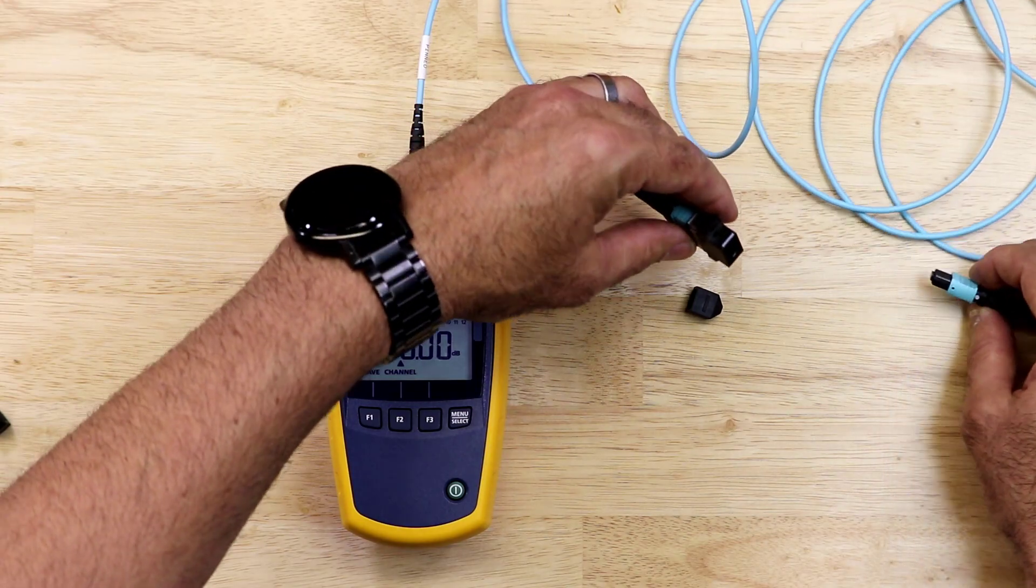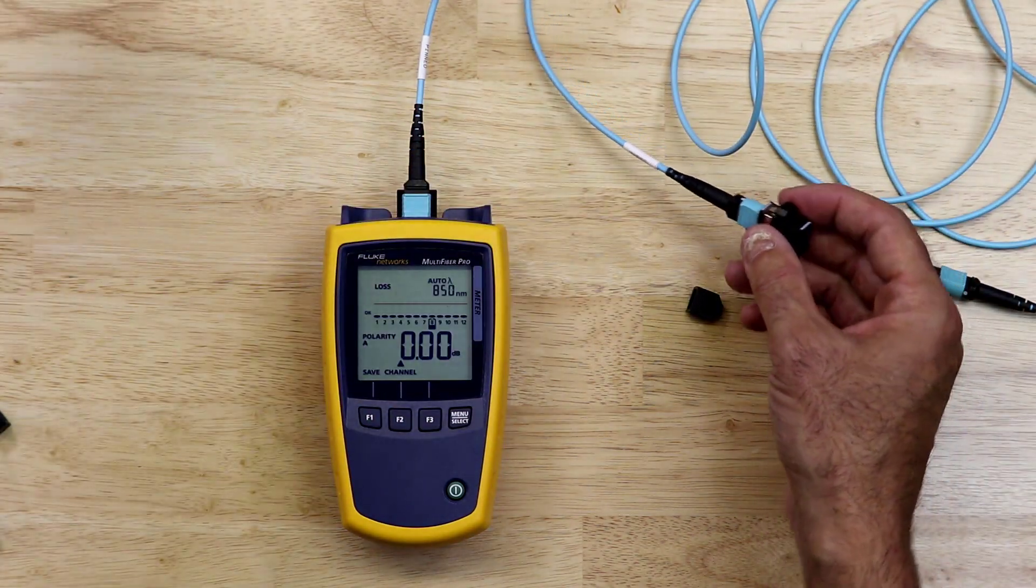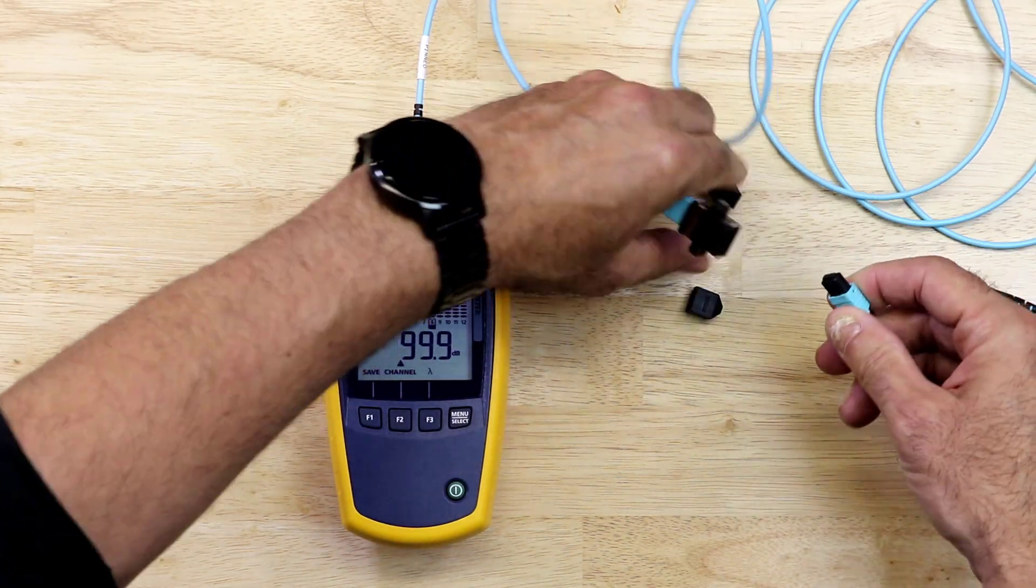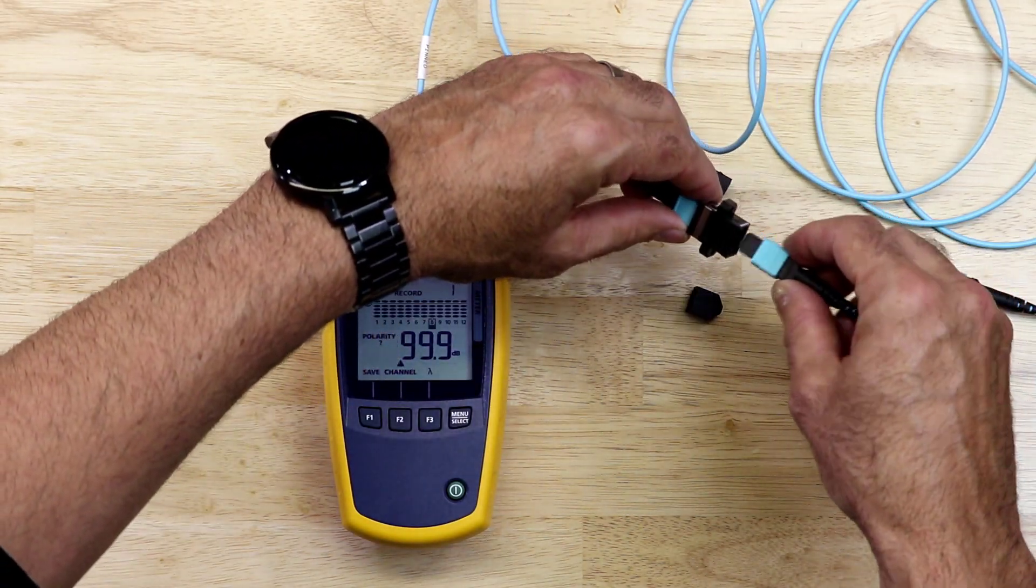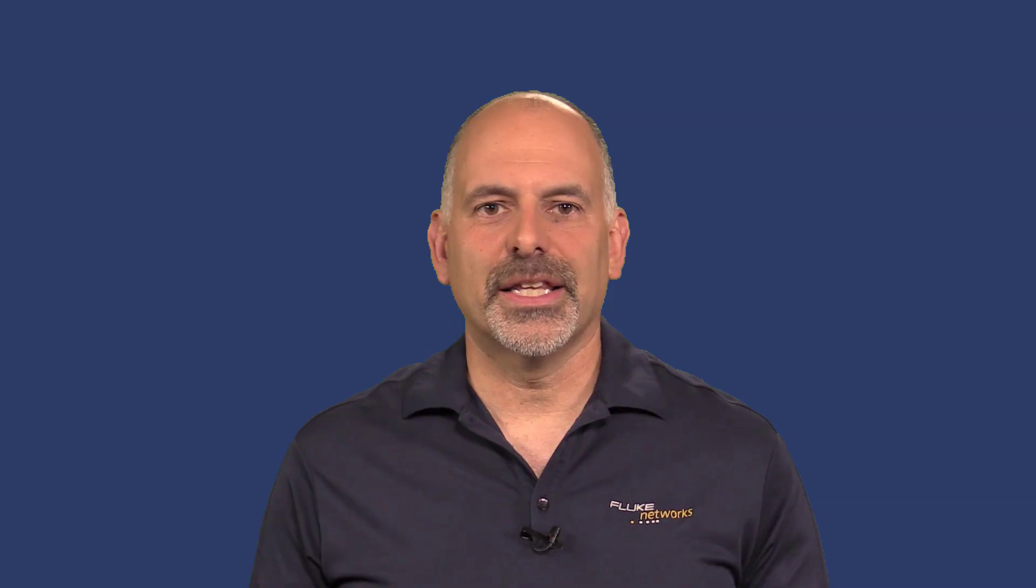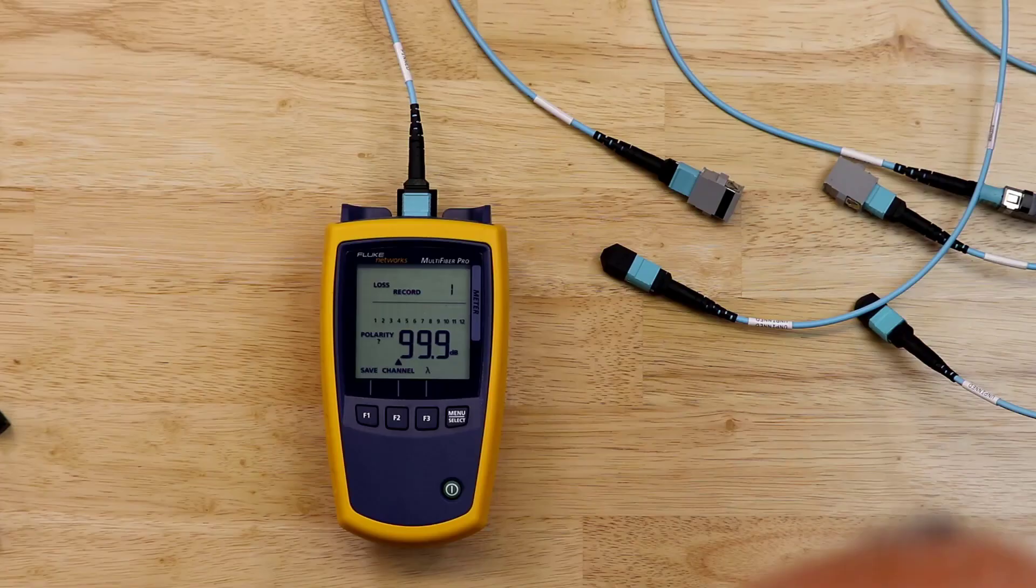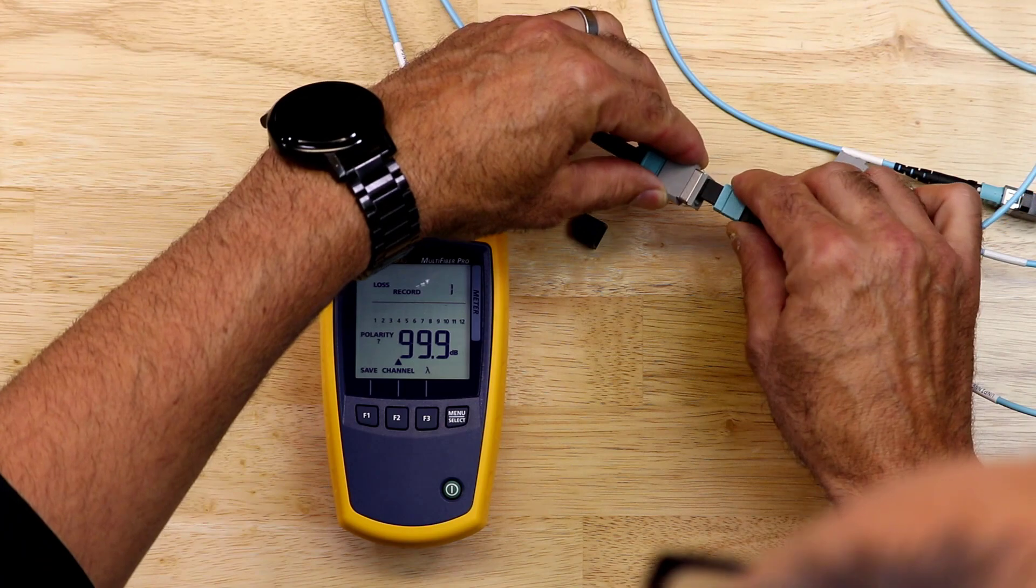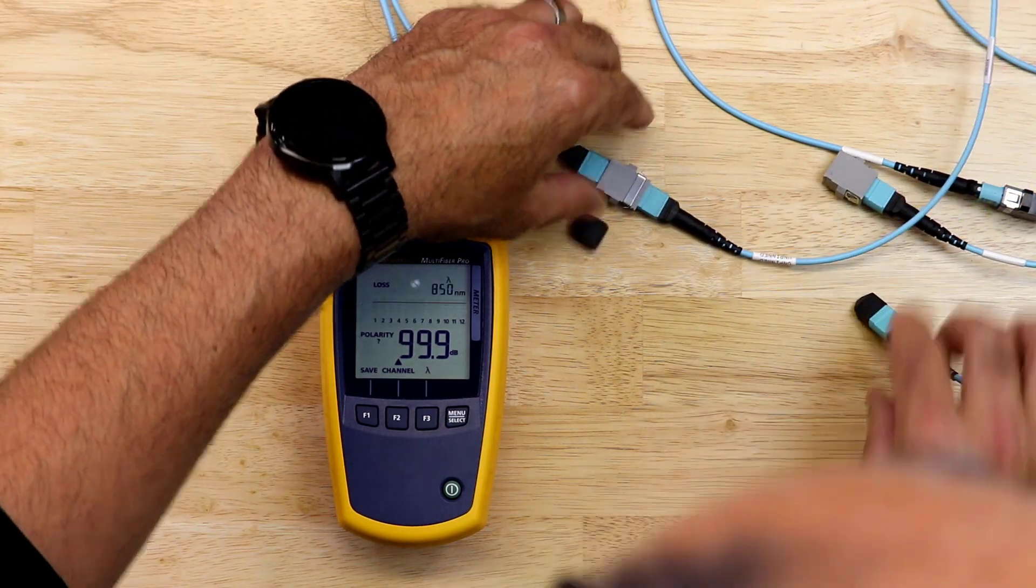After setting the second reference, I will disconnect the meter and the light source at the bulkhead connector. I'll connect the short, unpinned to unpinned test cable to the light source bulkhead connector. This gives me two unpinned connectors to connect to my pinned to pinned trunk cable. Upon connecting the light source and the meter to the link I wish to certify, the meter will begin measuring the loss.